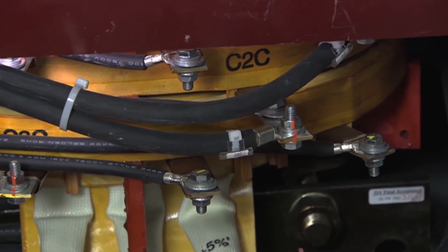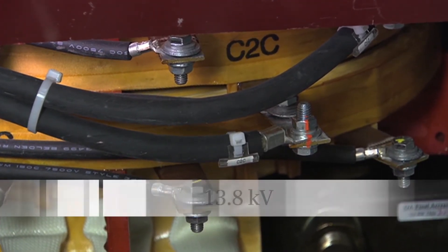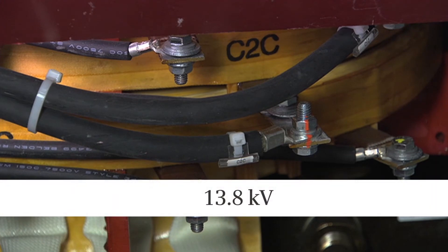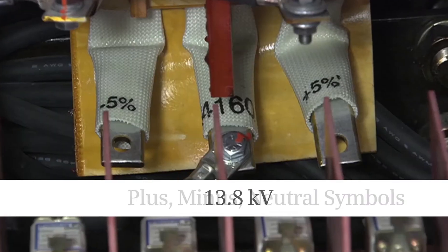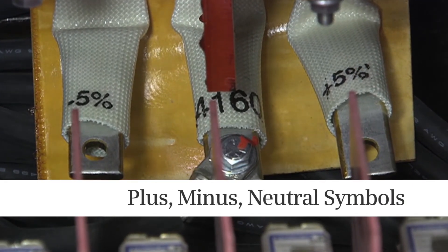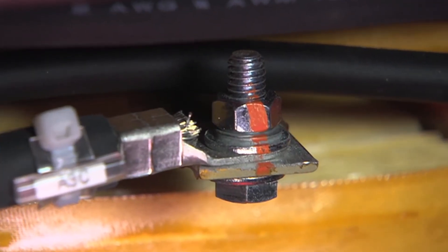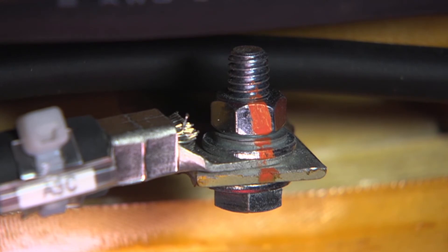The primary cable connects incoming medium voltage power to the transformer and can accept primary voltages as high as 13.8 kV. Plus/minus 5% taps are located at the primary windings, and secondary fuses connect to the power cells. All connections are torqued to a specified limit and marked per Siemens' extensive quality procedures.